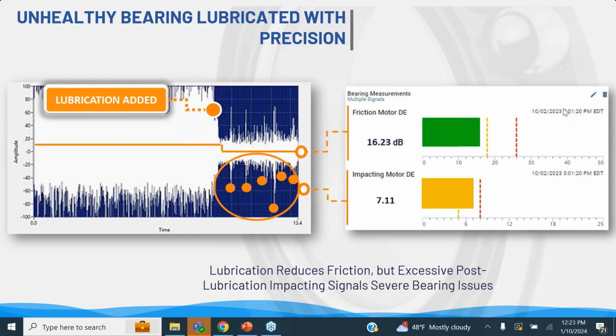One thing that's key here is that impacting is still warning. On an unhealthy bearing, the friction may drop, not to the level of a healthy bearing, but it drops. But the impacting is still high. So what we do here is we count the number of peaks and also the amplitude of each peak to give you a very unique insight into the health and lubrication needs of your bearing. While this bearing is unhealthy, it doesn't mean it needs to get replaced. But what you can anticipate is this bearing needing more grease more frequently.